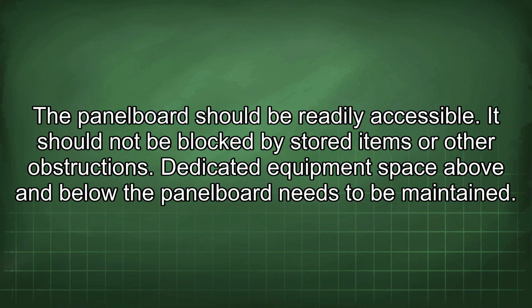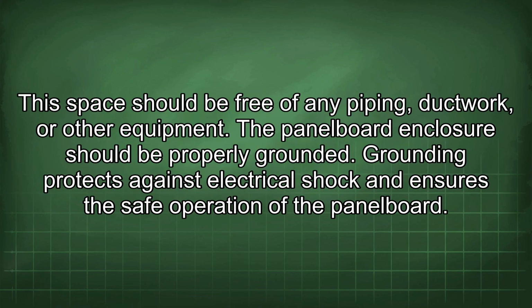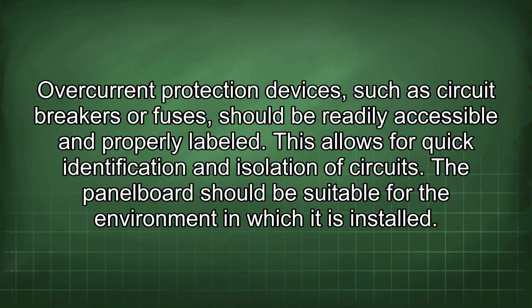It should not be blocked by stored items or other obstructions. Dedicated equipment space above and below the panel board needs to be maintained. This space should be free of any piping, ductwork, or other equipment. The panel board enclosure should be properly grounded. Grounding protects against electrical shock and ensures the safe operation of the panel board. Overcurrent protection devices, such as circuit breakers or fuses, should be readily accessible and properly labeled. This allows for quick identification and isolation of circuits.